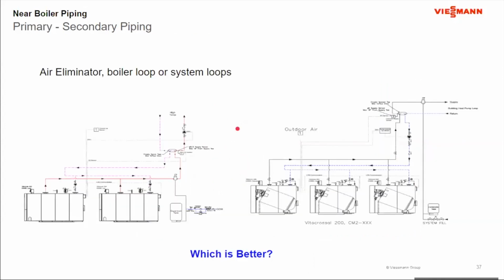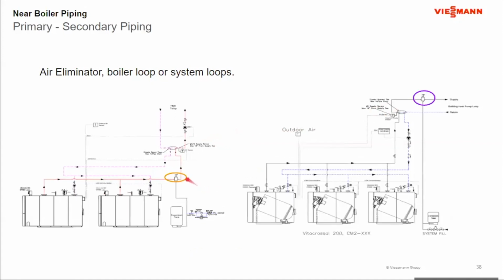Now, the next thing we want to touch on is the air eliminator. When we put drawings together, our drawings, I would say for the most part, tend to show the air separator or the air eliminator on the boiler loop when I'm doing primary, secondary. Occasionally, we'll put it out here on the system loop. A lot of times that's because somebody either sent us a hand drawing that had it out there or somebody requested it. And the question always comes up, which is better? And the answer can be neither one is better, or one or the other is better. But I want to point out why the drawings tend to show it here rather than out there.